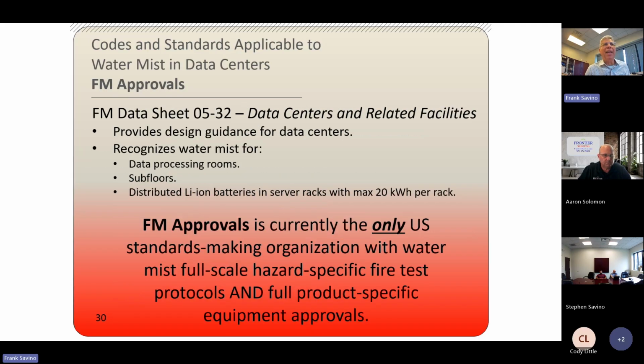Data sheet 5-32, titled Data Centers and Related Facilities, provides design guidance, and it has everything from material of construction and spacing between equipment to issues regarding lithium-ion batteries in server racks. So really, the takeaway of all these different codes and standards is Factory Mutual is really the only U.S. standard-making organization with water mist full-scale, hazard-specific fire test protocols and full product-specific equipment approvals. So that's really where you have to go. You're not going to find it anywhere else. So that's where you have to go.